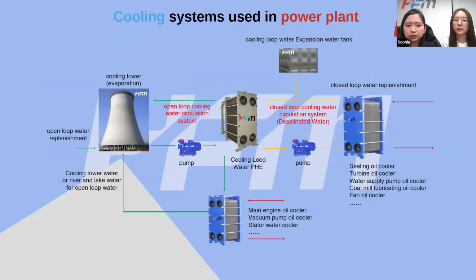So this diagram shows the cooling systems used in the power plant. As you can see, there are two main cooling water circulation systems. One is the open loop cooling water circulation system, and the other is the closed loop cooling water circulation system. We are going to begin with the open loop system. The water source comes from a river or lake and is pumped into the cooling tower for evaporation of the water. The cooling tower replenishes the water source to ensure the continuous operation of the cooling system.